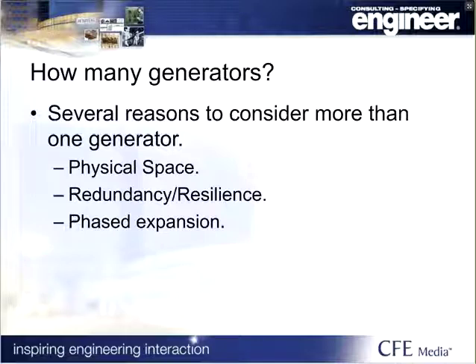Sometimes you may consider installing more than one generator to address emergency and standby loads. It could simply be due to the peak loading of your EPS exceeding available standard ratings of individual generators, or the project may have requirements for additional resiliency in the design should a generator fail.